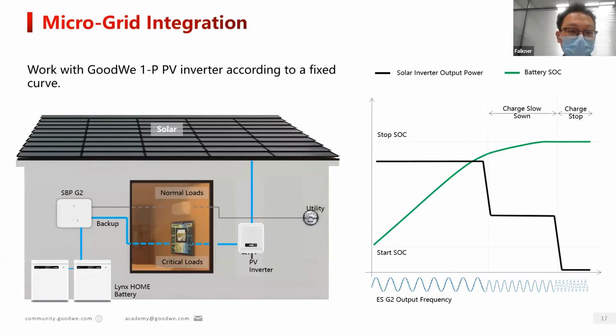Next is the microgrid integration function. This function means you can connect a PV inverter on the backup side of SBP G2. During the daytime, the PV inverter will charge the battery and support the critical loads working. And once the battery is charged to 100% SOC, ES G2 will increase the output frequency to reduce the PV generating power.